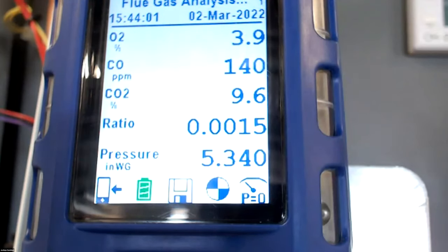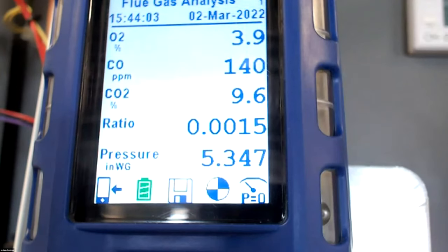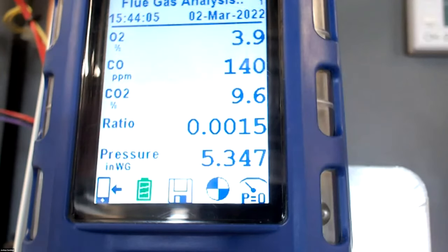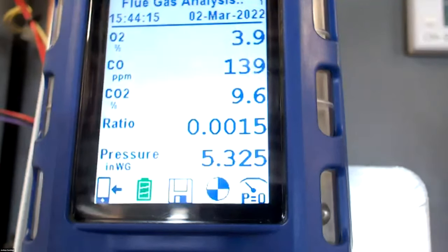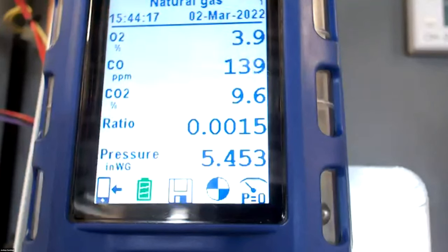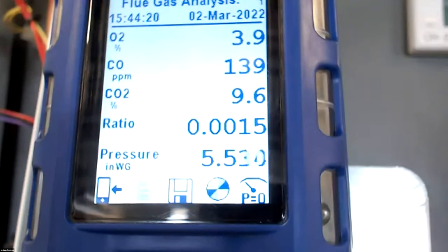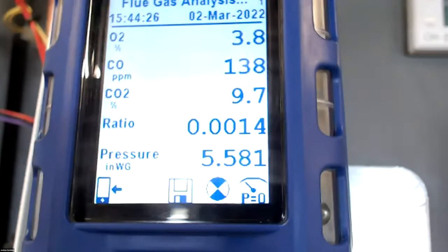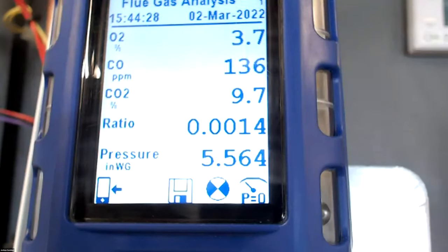So the next thing I'm going to do is bring it into low fire. So I'm going to hit the left arrow and bring this back down to 1%. Now, when I do this, I'm not going to just go all the way down to one. I'm going to bring it down to like 75. Watch my gas pressure. Should see that steadily go up, not jump around everywhere. That way I can make sure my regulator is doing what it's supposed to.